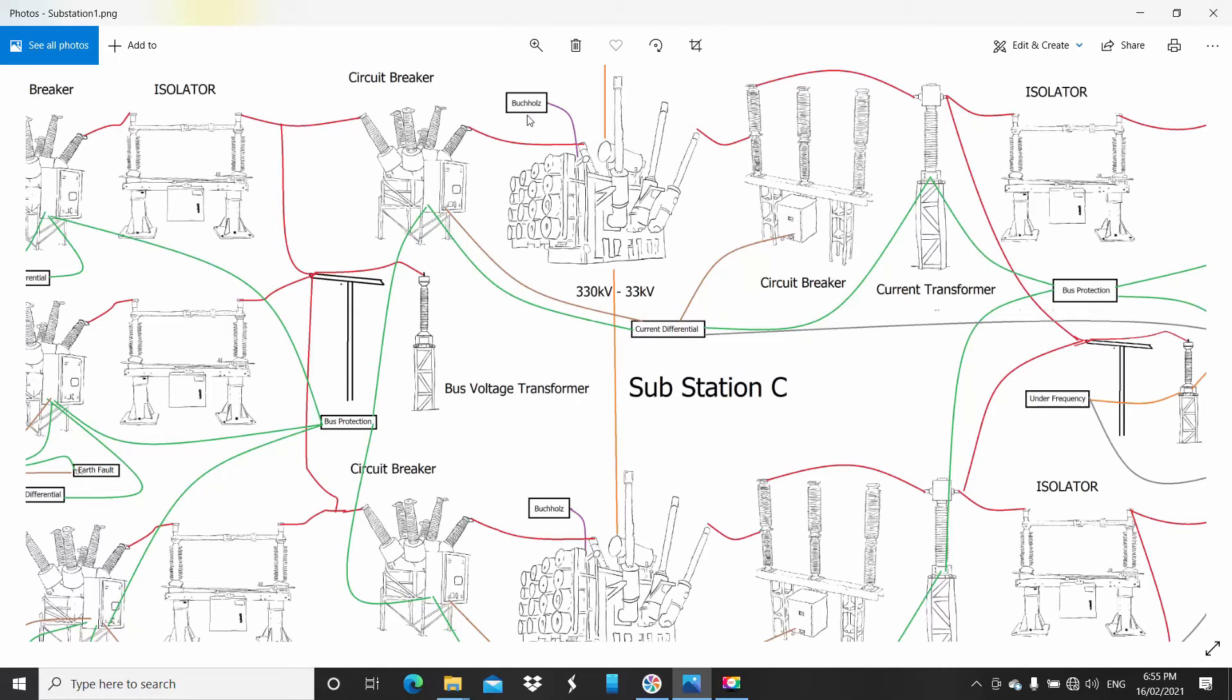To protect the transformer, we have a Buchholz relay up here. That does gas sampling of the oil, so it can start to see if it's breaking down inside. That's what that does. It takes samples as it goes through to the conservator. Then you have a current differential system. That's like the line, but because a transformer has two different voltage levels, two different potentials, it has two different currents.